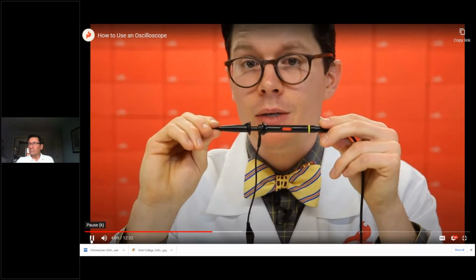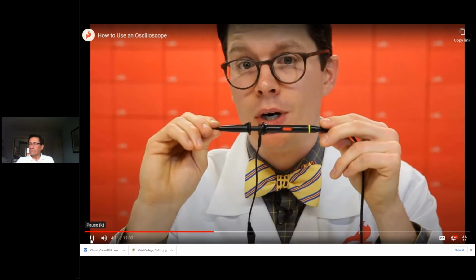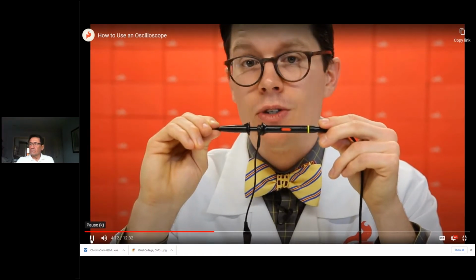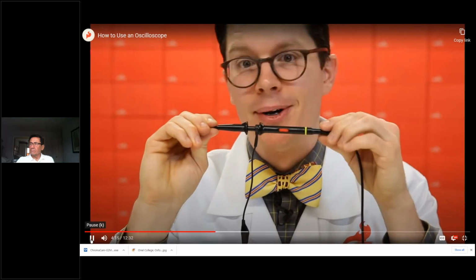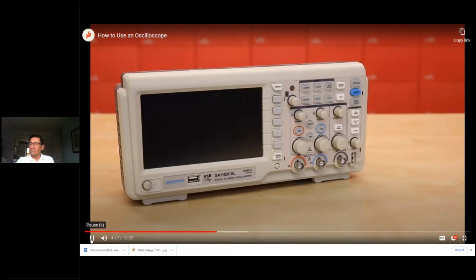However, that does mean we need to tell the oscilloscope that we're using a 10x probe, and we need to tune the compensation capacitor inside the probe. You'll likely only need to tune your probe once, but it's a good idea to check them every now and then to make sure that the compensation capacitor didn't get adjusted by your lab partner or some spooky ghosts. To start, select the 10x setting on your probe and plug it into the oscilloscope.